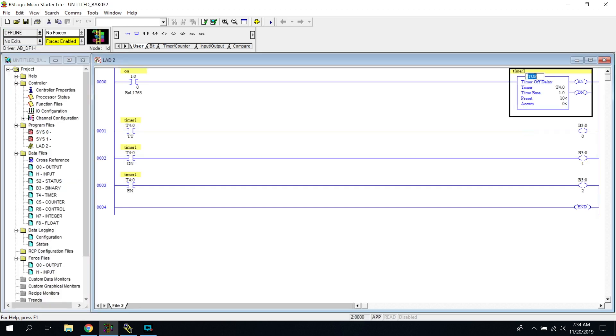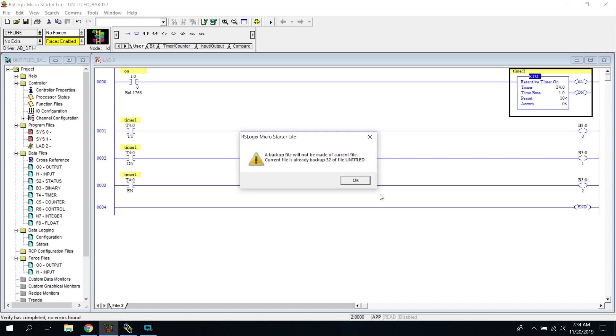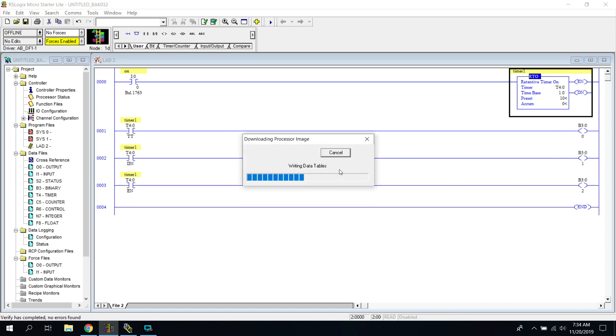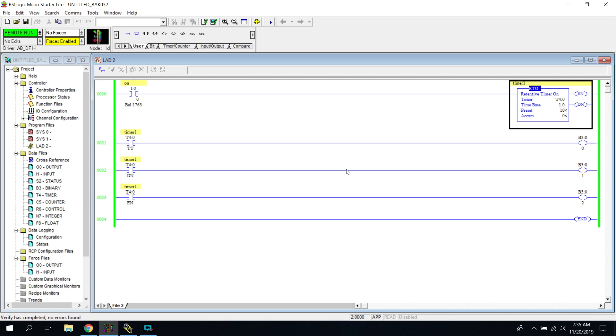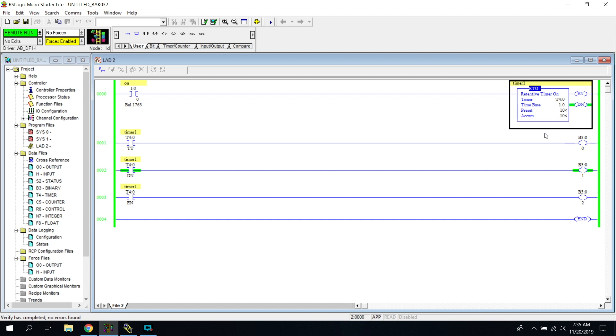Let's go offline and throw in the retentive timer — RTO — and download. When I press the button it starts accruing time. When I release the button, notice it keeps those seconds — it's retaining that time. I press the button again and the instructions keep working based off the accumulated value. When it hits 10 it's done. Notice that if the rung becomes false, it does not reset itself. We actually have to go in and put a reset bit in — I'll explain that when we get to the retentive timer in detail.